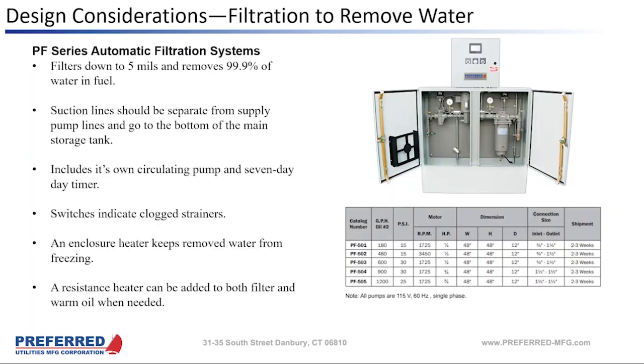So we talked about this a couple of times. Water in your fuel really changes the lower temperature limit of your fuel from the normal cloud point of 14 to 18 degrees up to about 32 degrees. So it's really important to keep the water out of the fuel. And we make 5 sizes of fuel polishers that take the water out of the fuel and then take all the chunks out of the fuel too. The final filter element can be anything you want. I think our standard is a 10 micron filter, but that's a replaceable filter. We can put any size filter or any grade filter you want in it.